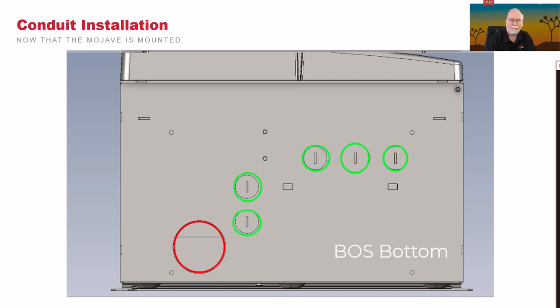Again, there are four 3/4 inch knockouts and one 1 inch knockout. There's also a 2 inch opening in the very bottom. This is for the battery. These are all the DC connections. So the only thing running through this should be the DC ground, the negative, the positive, and whatever CAN bus or other connection that you need. A temperature probe should run through that adapter.